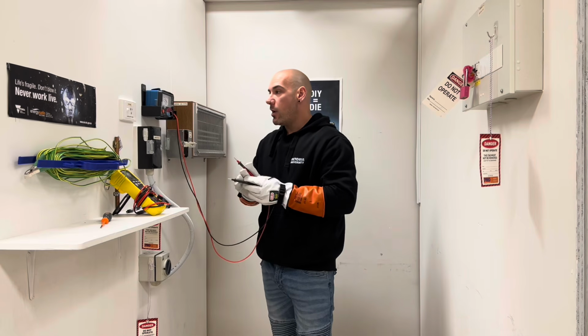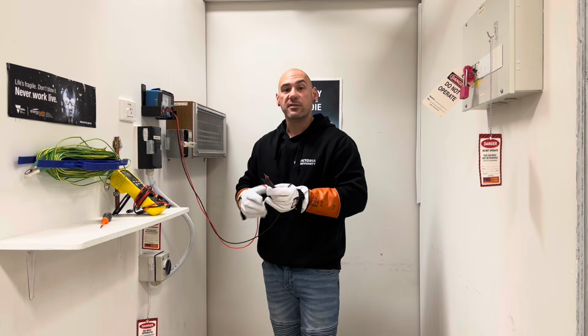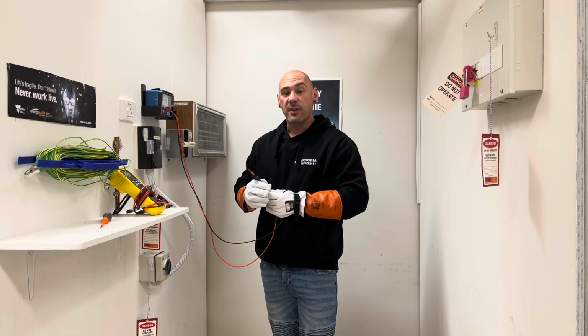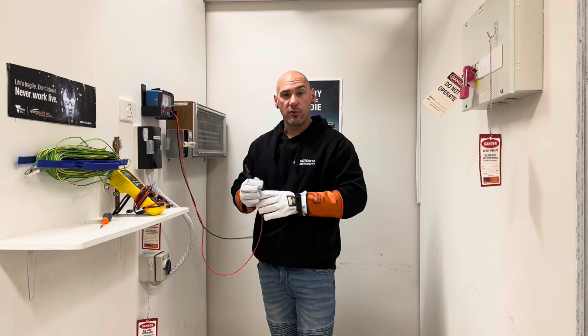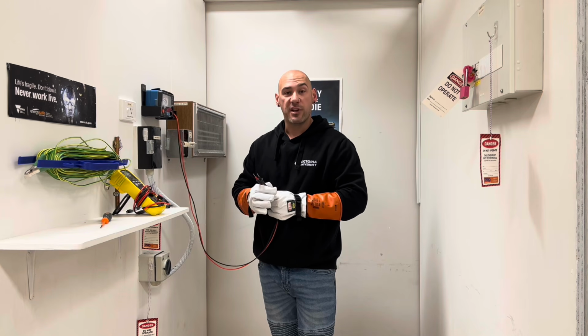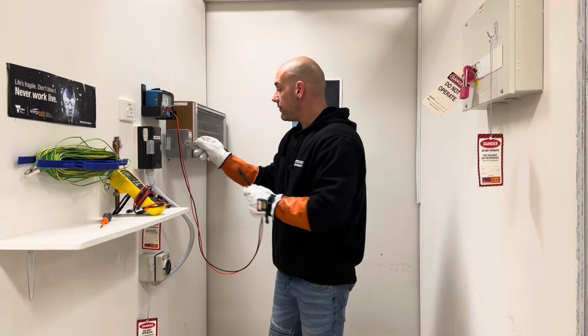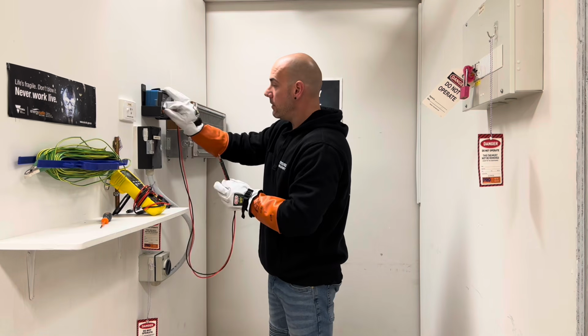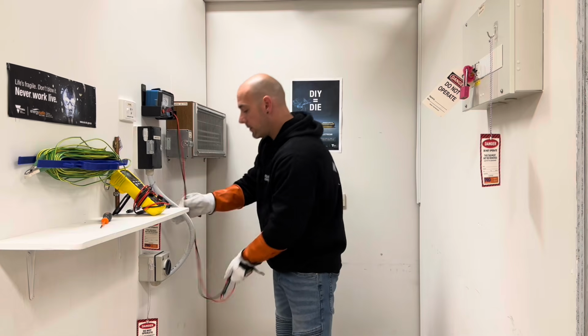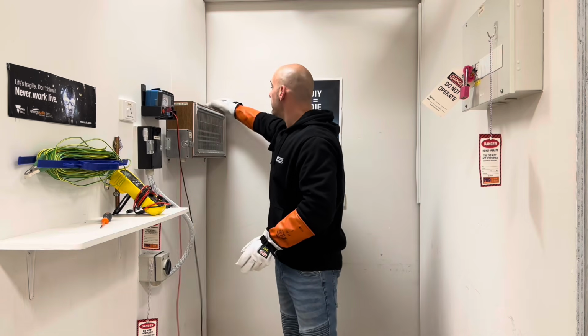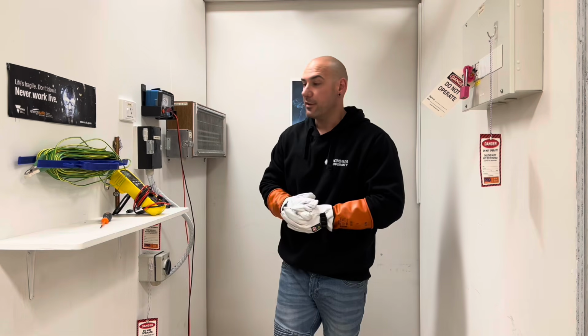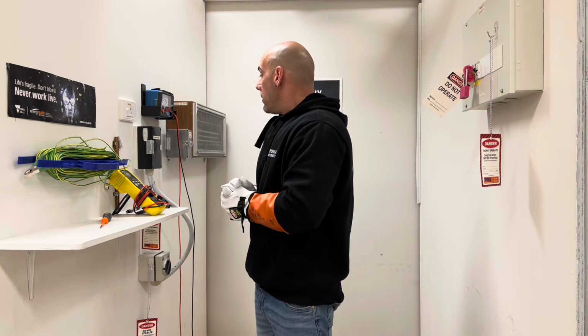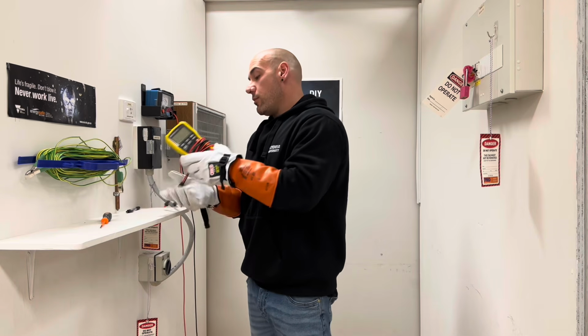The minimum IR test for an appliance is 1 megohm, but this can be also as low as 10,000 ohms or 0.01 megohm for anything with a sheathed element. Okay, so that appliance is safe to reconnect. It's time to reconnect the cable.